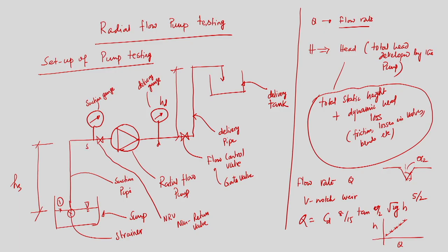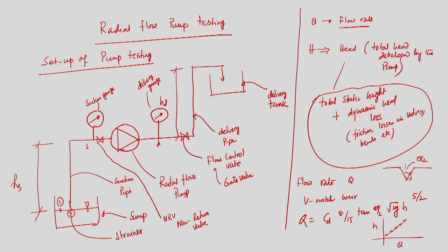This is quite obvious, because if air is inside the impeller, and if I go back to my previous slide, the atmospheric head is the only available head. If air is there, it is very difficult to have any driving force between point 1 and S, so that water will go away. So, to ensure that, we have the priming operation, which is done before we start the pump.